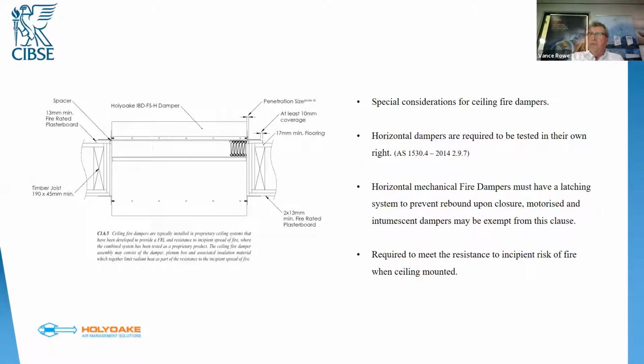Fire dampers are available in vertical and horizontal orientations. Horizontal fire dampers are required to be tested in their own right. That's listed under clause 2.9.7 in AS 1530.4. Horizontal fire dampers also must have a latching system within the damper itself so that they don't bounce back upon closure. And it's absolutely critical that people understand the correct orientation to install a horizontal fire damper, as most of them will latch from one side only.